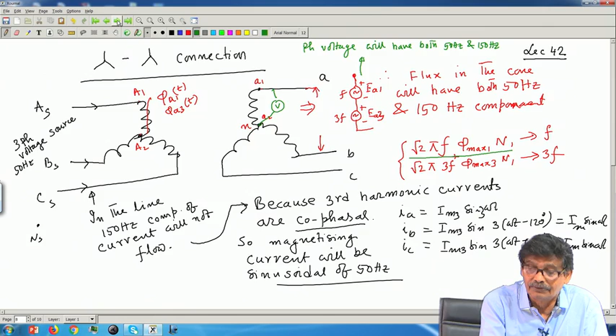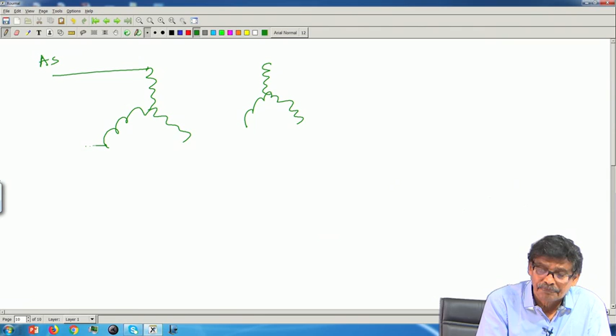Therefore, in a star connection like this with no neutral connected anywhere, isolated, I have never connected the supply neutral. But I can tell you one thing about this. Suppose this is the primary star, this is the secondary, with B S and C S drawn, and the supply neutral, listen to this point, I have also connected to the primary neutral. This connection is slightly different: a balanced 3 phase voltage to this and also the neutral. Supply voltage is a balanced 3 phase voltage.